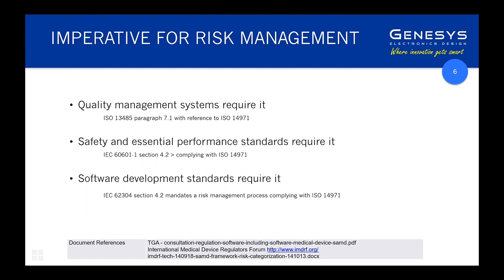The right answer is so that we can develop safe and effective medical devices where we have considered the risks that those devices pose and dealt with them in the design and development phase. And of course the subsequent production and deployment phases. The happy byproduct of that is that in doing so, we comply with the medical regulatory standards, which is a necessity to enable us to gain certification for sales of that product legally in various jurisdictions.